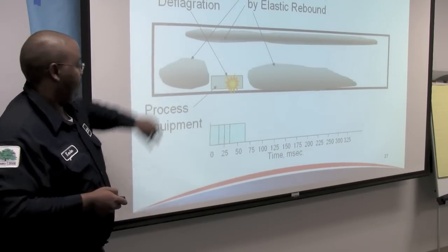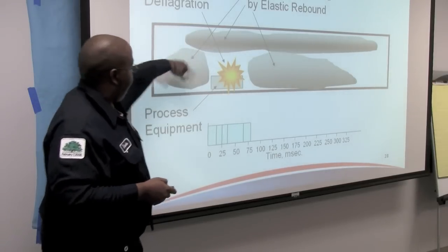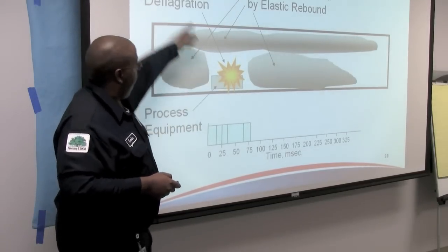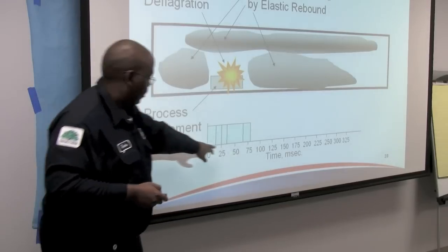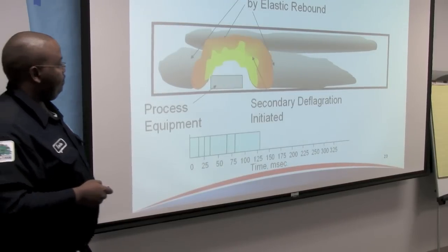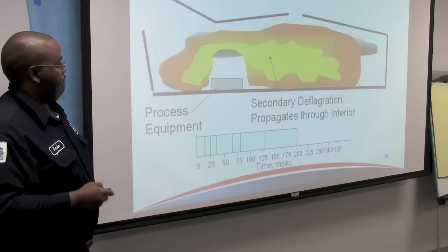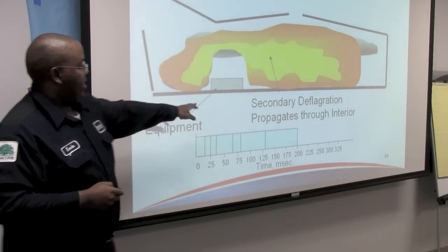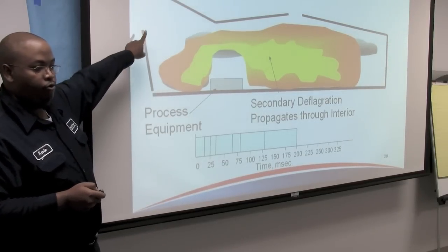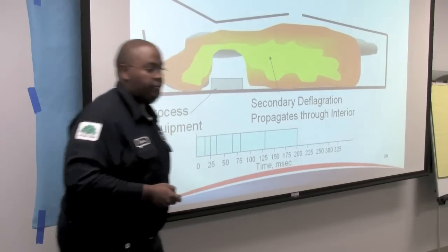A dust cloud caused by the rebound waves leads to containment failure from the initial deflagration. All of this is happening at just over 75 milliseconds. Then secondary deflagration is initiated and propagates through the interior — you start to lose containment and building structure — and we're at 200 milliseconds.